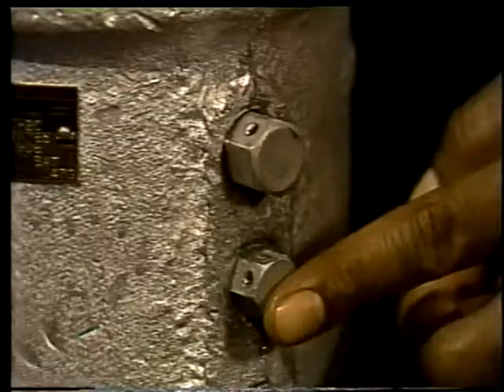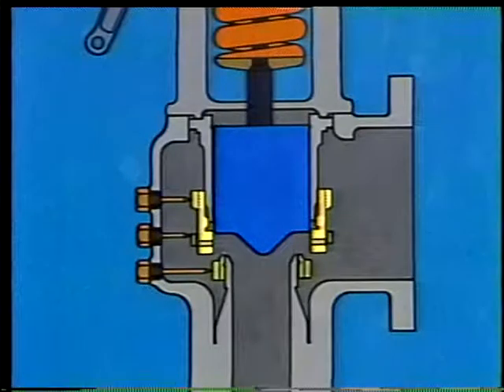It should be done only by an experienced mechanic who has consulted the manufacturer's instruction manual and knows precisely how the rings should be set. And once properly set, the ring should be locked in place by tightening the ring pins that protrude through the valve body. That covers a two-ring huddling chamber safety valve. Now, how about this one, the three-ring type?